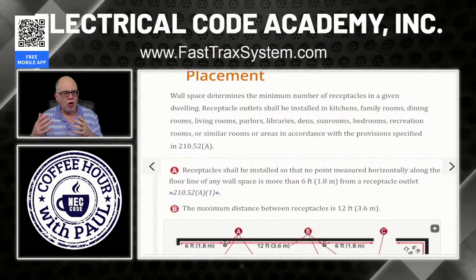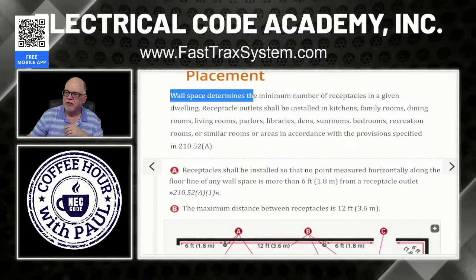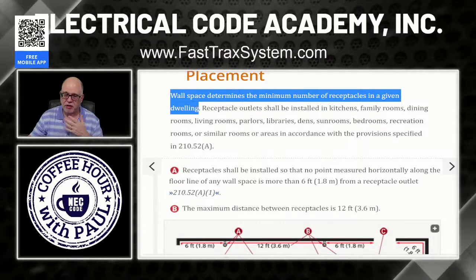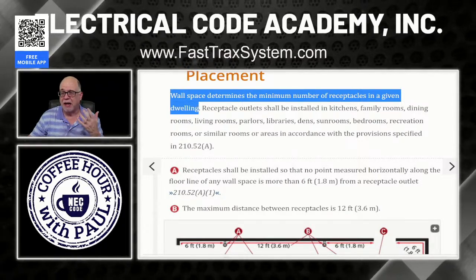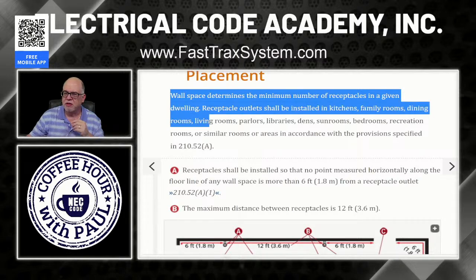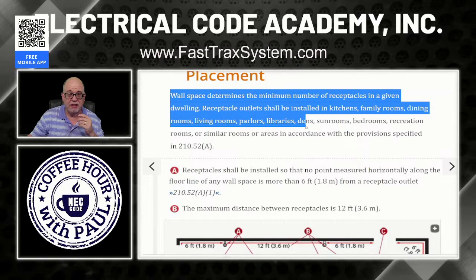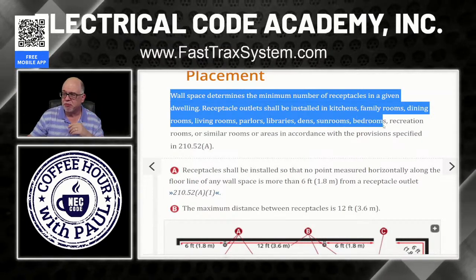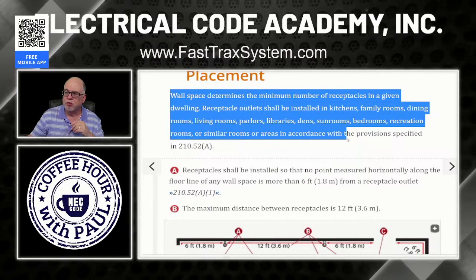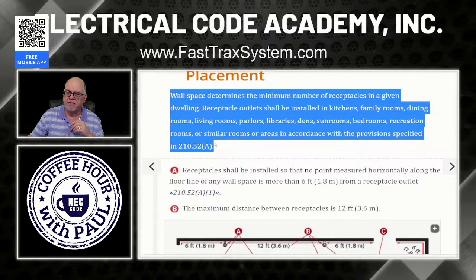So we're talking about bedrooms, living rooms, where we put these receptacles. Wall space determines the minimum number of receptacles in a given dwelling. How much wall space you have, measuring it out, is going to help define how many receptacles you actually have. Receptacle outlets shall be installed in kitchens, family rooms, dining rooms, living rooms, parlors, libraries, dens, sunrooms, bedrooms, recreation rooms, or similar rooms or areas in accordance with the provisions specified in 210.52(A).